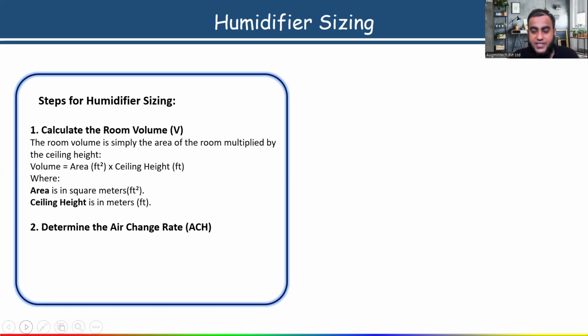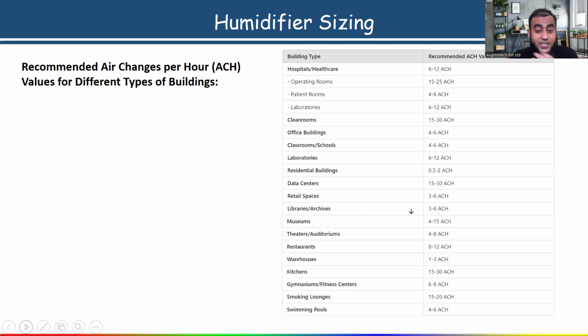Second, determine the ACH value, air changes per hour. In 1 hour, how many times do you have to change the air? The air changes value totally depends on the type of building, which type of building you are designing. So based on the type of room, select the appropriate ACH value from the table. You can see the recommended air changes per hour values for different types of building in this table, which I have taken from the ASHRAE 62.1 ventilation standard, or some recommended ACH values are taken from ASHRAE 170, generally the ventilation standard for healthcare facilities.